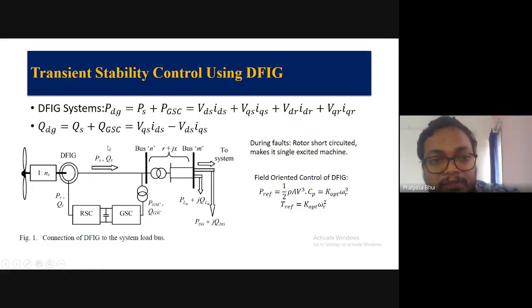equation for reactive power. Now the power in the wind is half rho A v cube. So wind power is proportional to the cube of the wind velocity v multiplied with the coefficient of power Cp. Cp is basically the efficiency of the wind turbine. Now this power reference is half rho A v cube into Cp. So the control action should take care that the wind generator gives this much electrical power. So the mechanical power is half rho A v cube into Cp. Now the electrical power should be equal to that. So this is the reference to the controller.